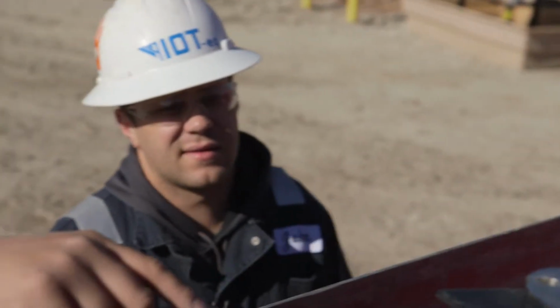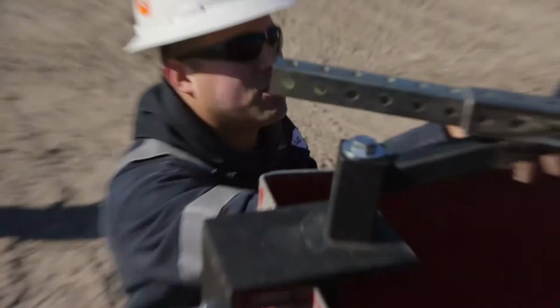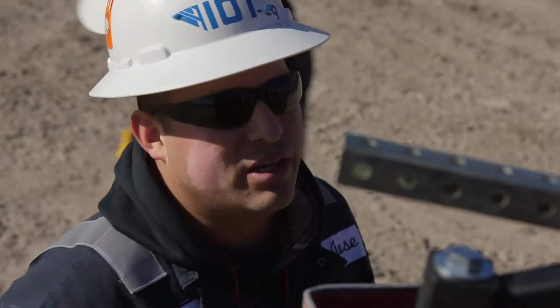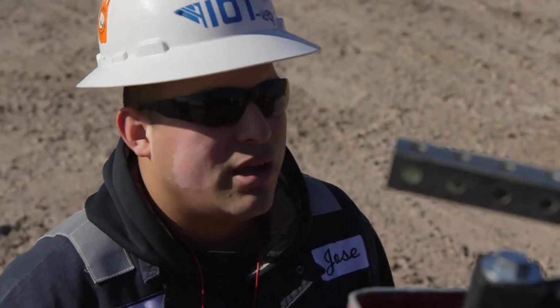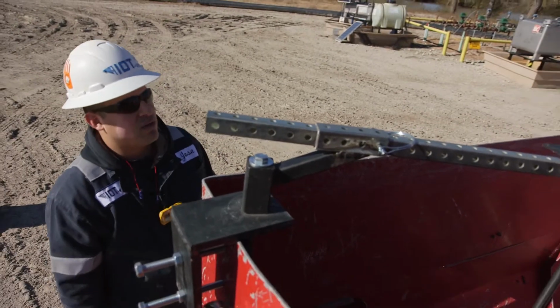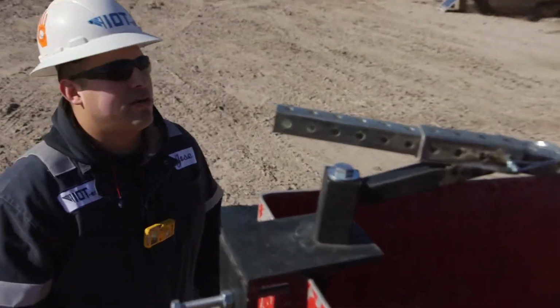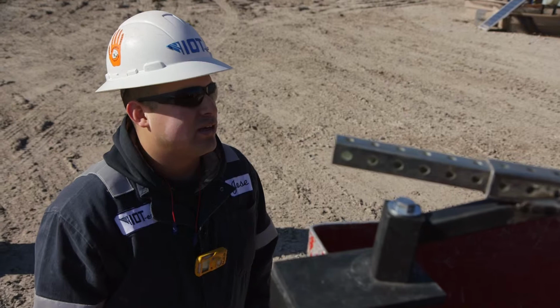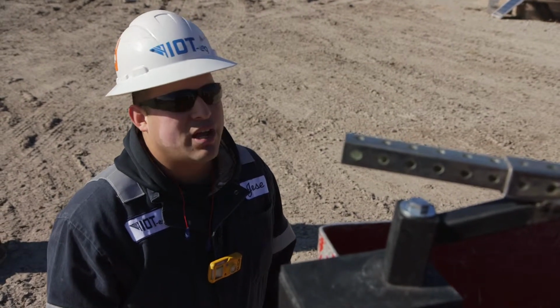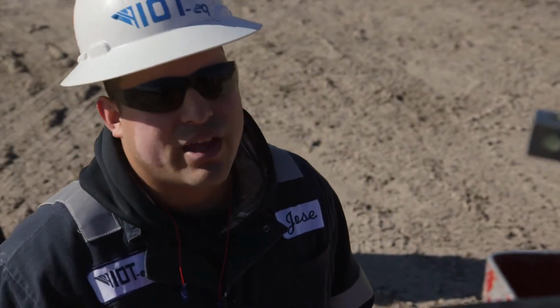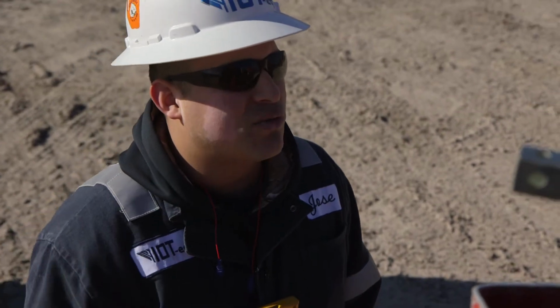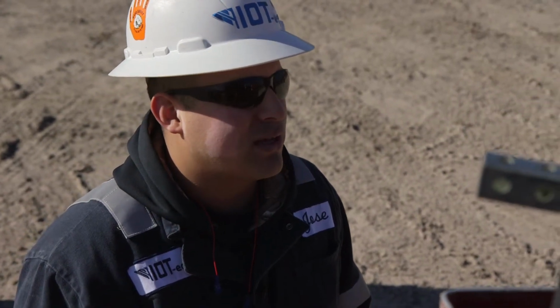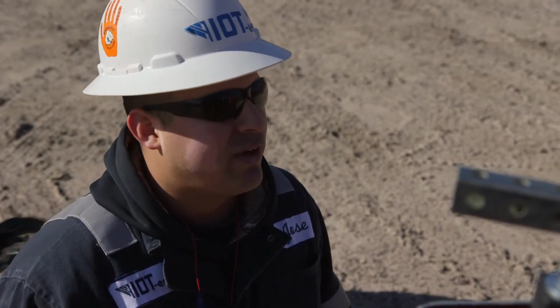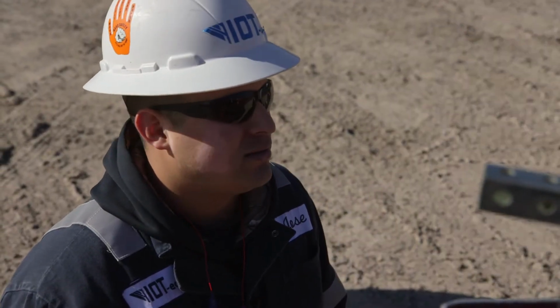What we'll do from here is connect each probe cable to our junction box, and once we power up the system, we can go ahead and calibrate our probes. We'll need to zero them out, and if there's a grate in the way, we'll have to do a false signal suppression to account for that, make sure we can get a nice clean reading, test it, and find a good set point for our sand.